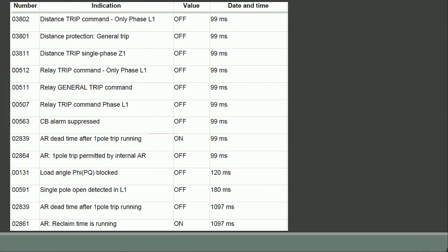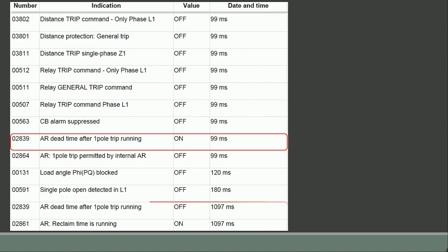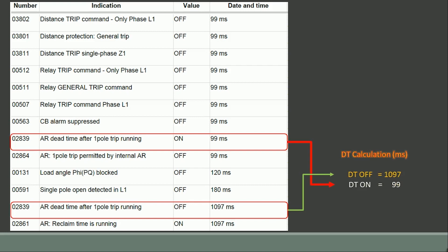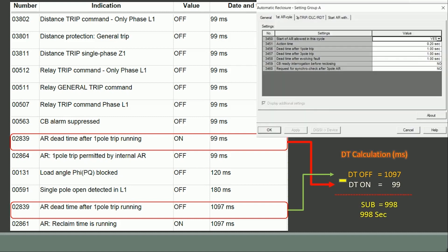The auto reclose dead time is started at 99 milliseconds as per parameter number 02839 and it's turned off at 1097 milliseconds as highlighted. The difference between the dead time off and the on time provides the approximate 1 second dead time configured in the relay.